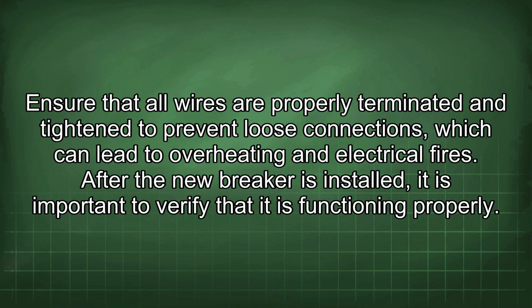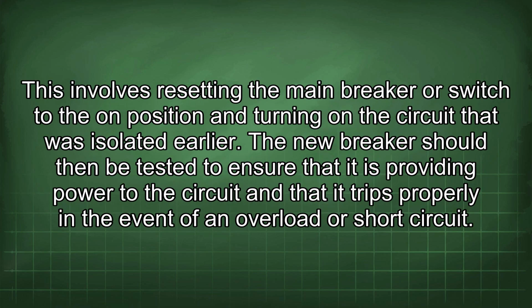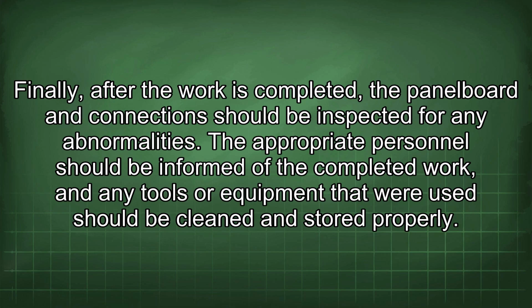After the new breaker is installed, it is important to verify that it is functioning properly. This involves resetting the main breaker or switch to the on position and turning on the circuit that was isolated earlier. The new breaker should then be tested to ensure that it is providing power to the circuit and that it trips properly in the event of an overload or short circuit. Finally, after the work is completed, the panel board and connections should be inspected for any abnormalities.